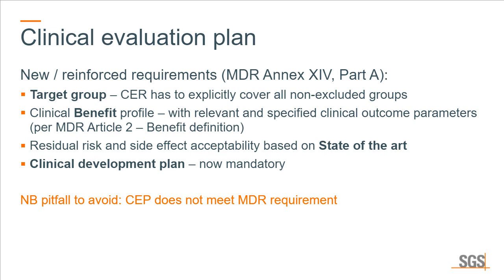So if your intended use in your IFU and in your marketing materials allows this device to be used by everybody, then we will look for a clinical evaluation report that explicitly addresses all user groups. So if we will see that you have never checked whether the device can safely be used by pregnant women, the notified body is going to challenge that clinical evaluation report and will ask you to either mark that as a contraindication or get more clinical evidence that the device indeed can safely be used for that user group.